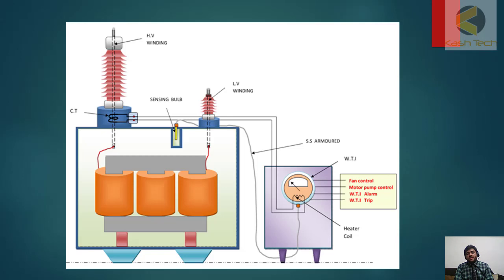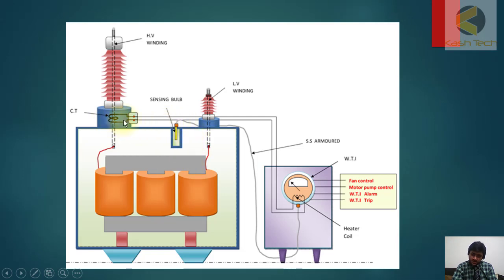The reason we cannot put a sensor directly in the winding is that the winding is high voltage — it is not practically possible. Instead, manufacturers use a sensor that monitors temperature near the winding. A CT (current transformer) is connected, and a heater coil simulates the winding: more current means more heat generated. By this simulation, the gauge operates to indicate winding temperature.